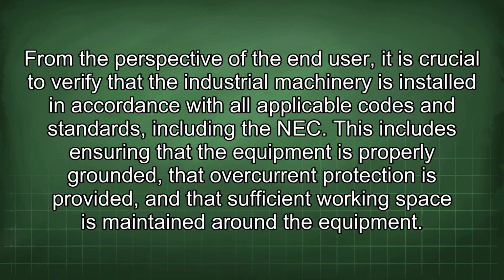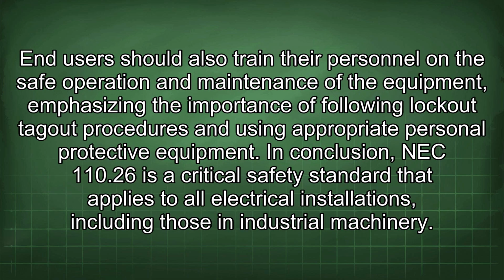From the perspective of the end user, it is crucial to verify that the industrial machinery is installed in accordance with all applicable codes and standards, including the NEC. This includes ensuring that the equipment is properly grounded, that overcurrent protection is provided, and that sufficient working space is maintained around the equipment. End users should also train their personnel on the safe operation and maintenance of the equipment, emphasizing the importance of following lockout-tagout procedures and using appropriate personal protective equipment.